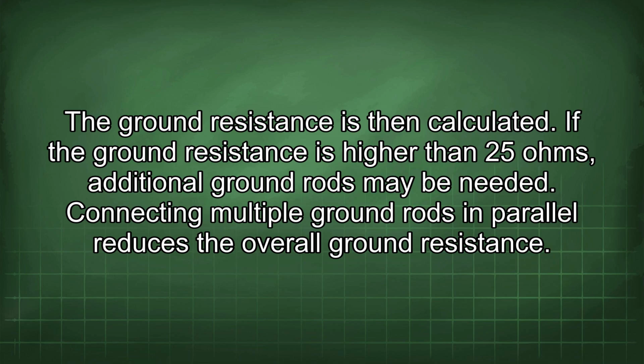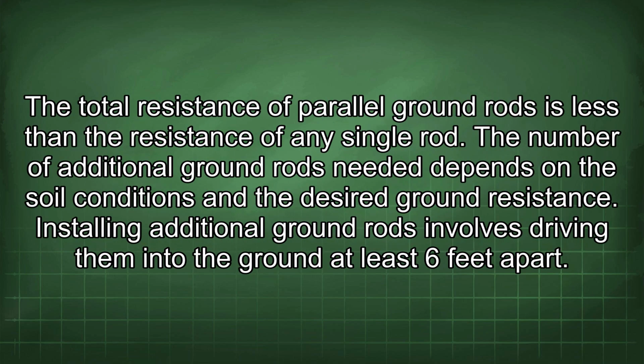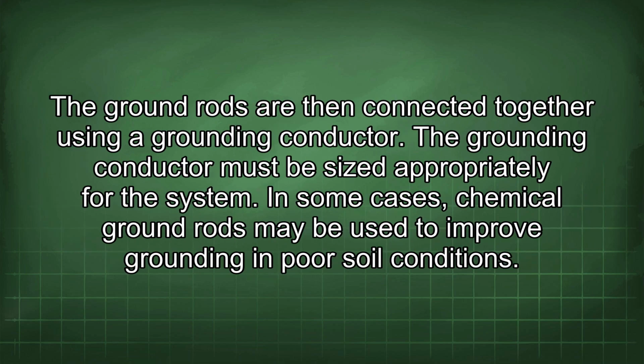Connecting multiple ground rods in parallel reduces the overall ground resistance. The total resistance of parallel ground rods is less than the resistance of any single rod. The number of additional ground rods needed depends on the soil conditions and the desired ground resistance. Installing additional ground rods involves driving them into the ground at least 6 feet apart. The ground rods are then connected together using a grounding conductor. The grounding conductor must be sized appropriately for the system.